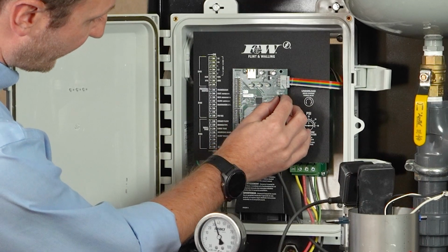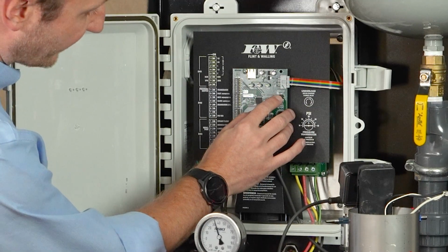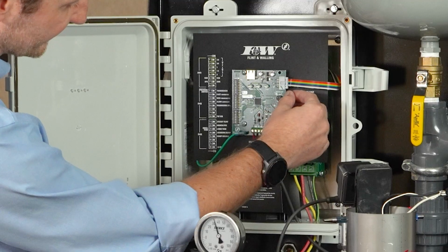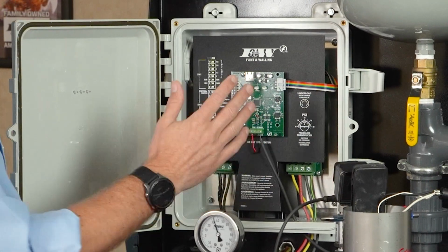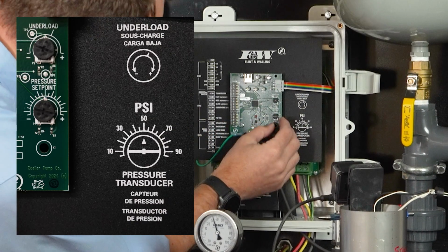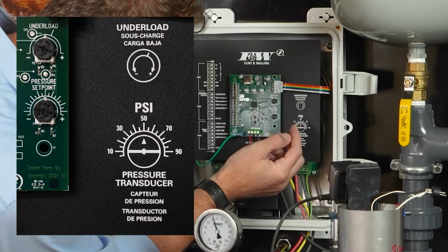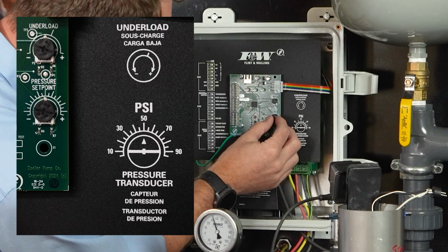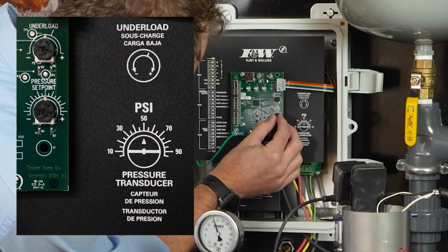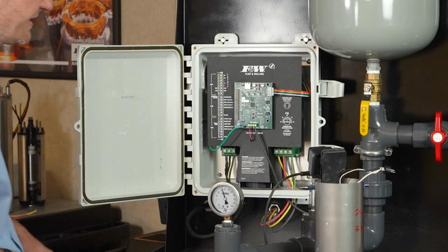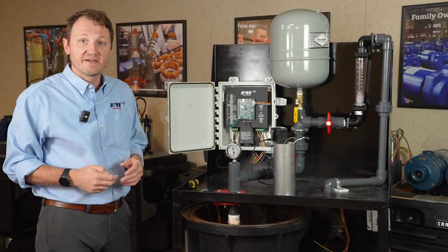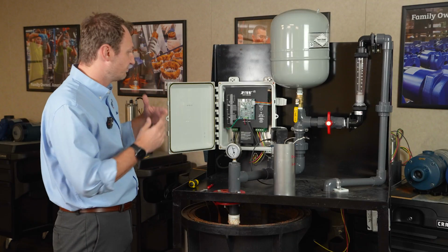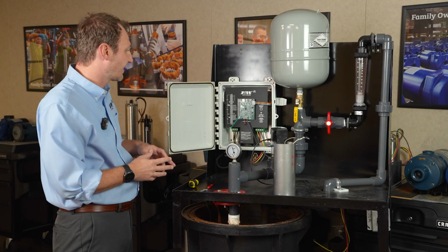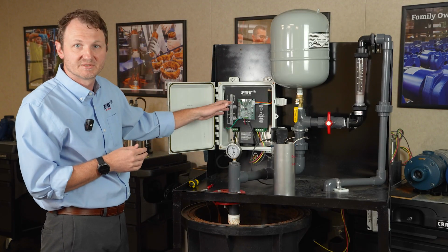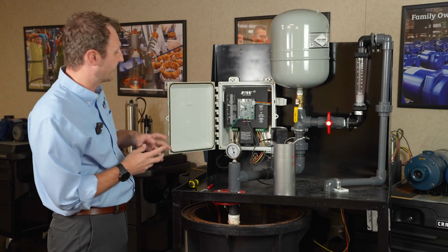I always want to confirm that my underload dial, there's a little arrow indicator on the dial itself, is lined up with the printed line on the actual board. And then here's our pressure set point. I've got it right now at about 50 PSI. We'll take that up to about 60 PSI there. And there you have it. That's installing the drive, hooking it up, wiring it up, just making your selections on the 3 dip switch banks. So we'll go ahead and close the lid here.